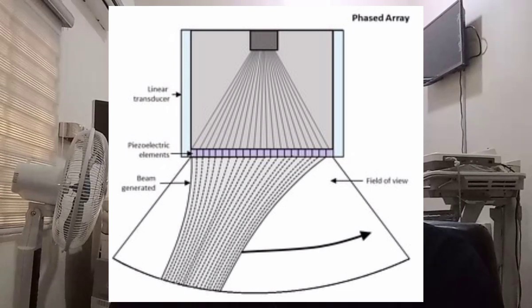The focal depth on the phased array system is controlled by the operator or sonologist. The ultrasound system alters the electronic pattern that excites the crystals; the pattern is changed for each successive sound pulse so that the beam can be swept to create the image plane. This sketch shows how the beam is changed in direction to create a single image.